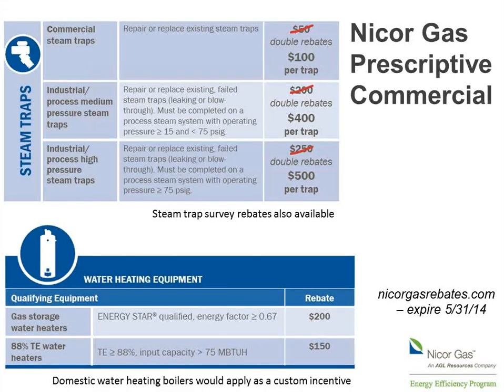Commercial steam traps. This is a huge rebate for the NICOR program, and right now the steam trap related rebates are double what they should be. They're offering them higher because this is a very exciting technology to them in order to get a lot of therms for a very low cost. So basically the rebate for space heating is $100 per trap, and then some of the industrial rebates for higher pressures are either $400 or $500 per trap.